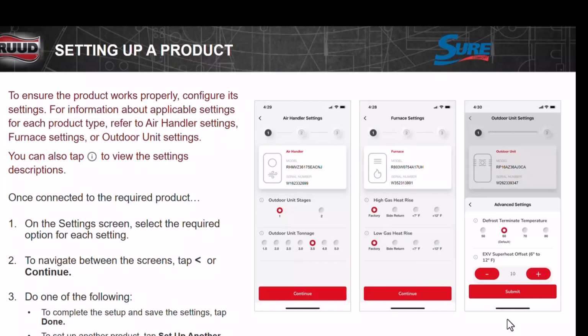This is where you can change it to, and I'm going to say this, and I don't mean anything negative by it, but if you have an elderly couple that's used to that really, really hot air coming out of the furnace, and a lot of the old furnaces put out a lot more heat than the 80% or 90% do today, that's where you can adjust this to, because they're used to that heat. You slow the fan down and get it hotter for them, right?